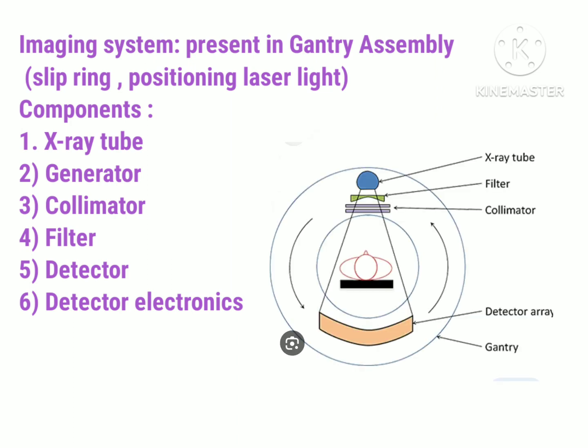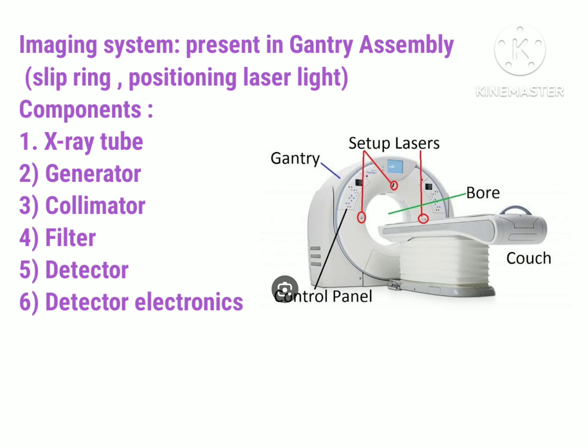The x-ray tube and generator both produce the x-ray beam. The collimator helps with the slice thickness of the image and also restricts scattered x-ray beams. The filter protects the patient from low energy x-ray beams and makes the beam uniform. The detector captures x-ray photons and converts them into an electrical signal. The detector electronics convert the electrical signal into digital form. This gantry assembly is a moving frame and the rotational components include the slip ring and the positioning laser lights.